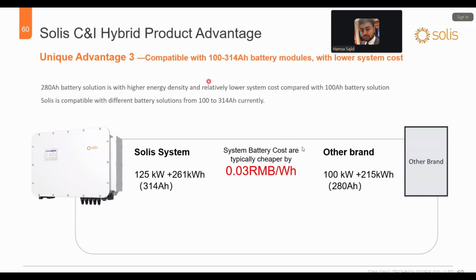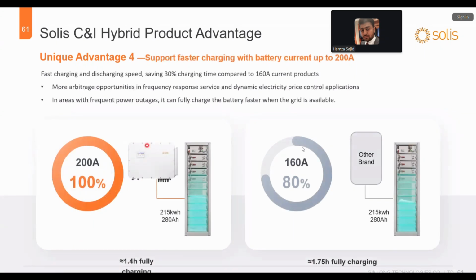Okay, this inverter is also compatible with 100 to 314Ah battery modules, which can easily save a lot of cost for you, to select a battery with a higher ampere hour rating. So the number of batteries utilized will be less. This inverter can charge the battery with 200 amperes. With the other brand, you can only go with 160 amperes. So it cannot fulfill the charge. It can only charge the battery up to 80%. But this inverter can easily charge the battery in fast mode with the help of 200 amperes.